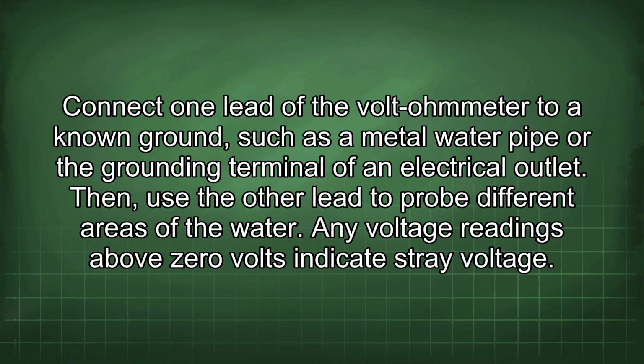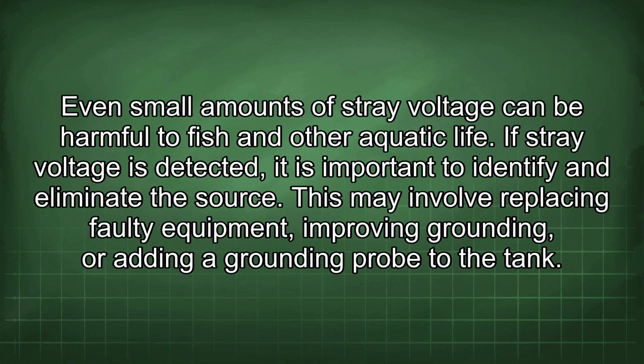Connect one lead of the voltmeter to a known ground, such as a metal water pipe or the grounding terminal of an electrical outlet. Then, use the other lead to probe different areas of the water. Any voltage readings above 0 volts indicate stray voltage. Even small amounts of stray voltage can be harmful to fish and other aquatic life.